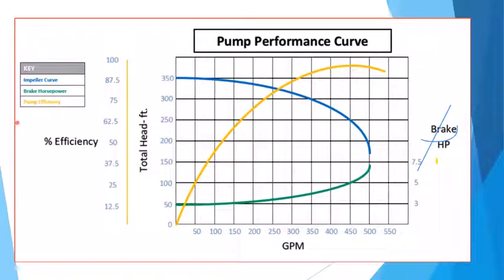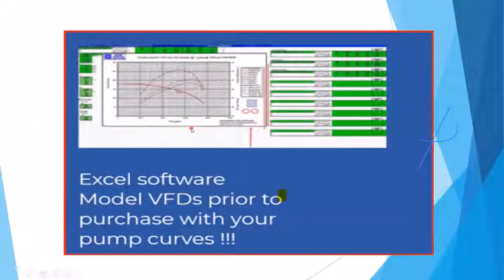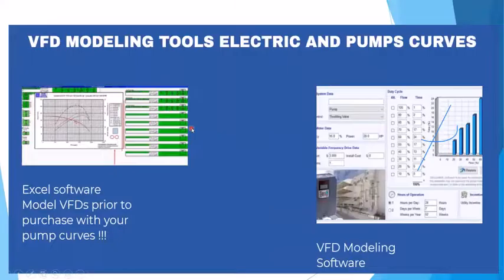I've seen guys that put wells in, in Nebraska in the early 50s and 60s, and some of them are still pumping. And so there's a big consideration. I don't think VFDs are bad. I think the issue is they have to be calculated for all the things that they're actually doing, and you have to look at the actual pump curve.